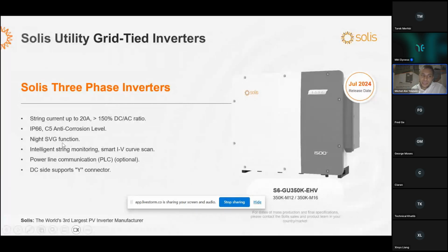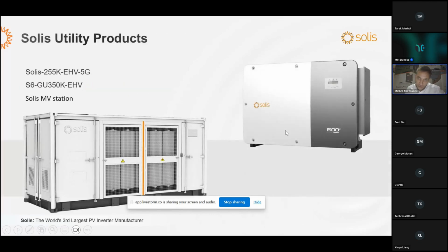Can support the SVG function also during the night. Also equipped with intelligent string monitoring and smart IV curve, like our commercial and industrial inverters. Also support the power line communication for monitoring, and can support also the Y connector on the DC side. The utility inverter also can be equipped with the MV station. We can also supply the MV station as a turnkey solution for the utility scale projects.